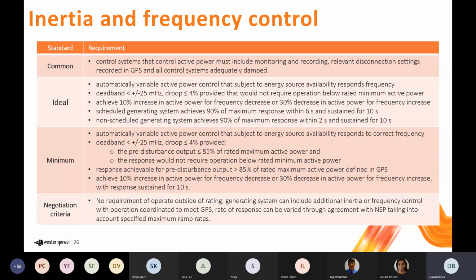So all large generating systems meeting the ideal performance standard must, subject to energy source availability, be able to automatically respond to correct frequency deviations with the response achieved having a better than 25 millihertz deadband and a droop that's 4% or better, provided that response wouldn't drive you below any technical minimums. In addition, if you're meeting the ideal standard, you need to be able to achieve a 10% increase in output in response to a frequency reduction and a 30% reduction in response to a frequency increase. And importantly, those responses need to be sustained.